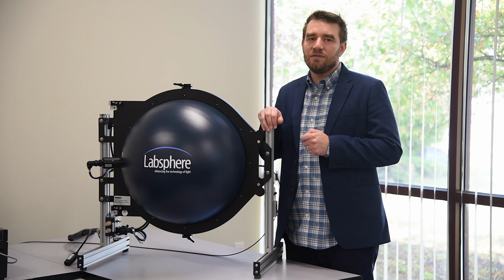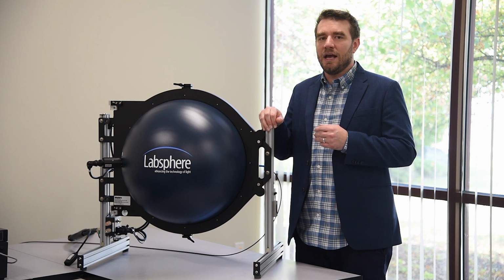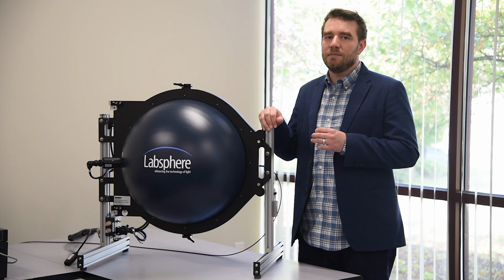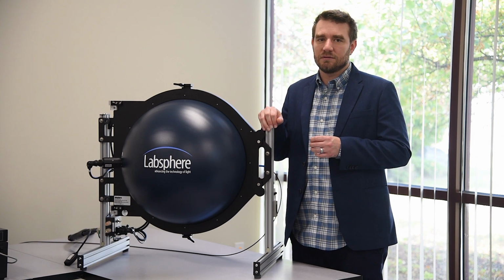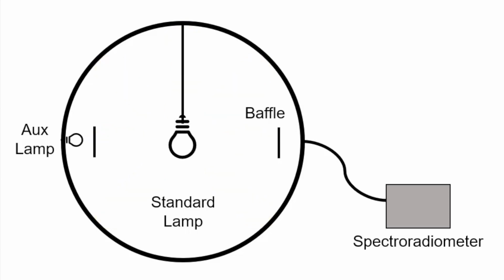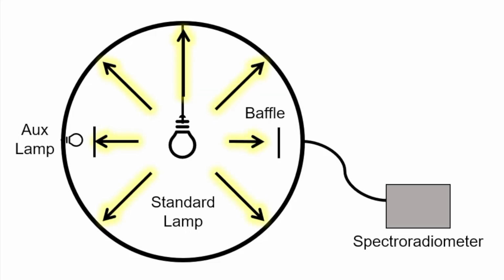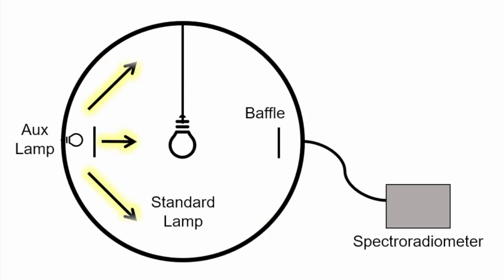So now, let's review the steps needed to make an absolute spectral radiant flux measurement using an integrating sphere. The first step in the substitution method is a measurement of the spectral radiant flux standard. For this measurement, the standard lamp is powered on and the aux lamp is attached to the sphere but powered off. The second step is a measurement of the aux lamp. For this measurement, we turn the reference lamp off and power on the auxiliary lamp.